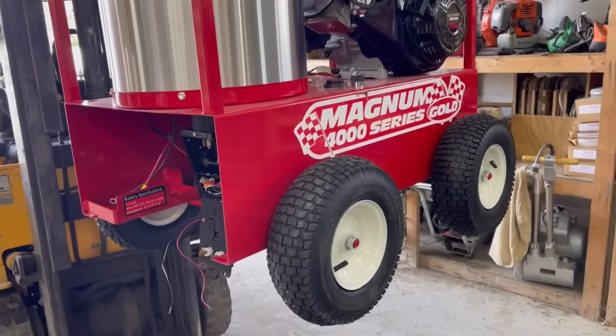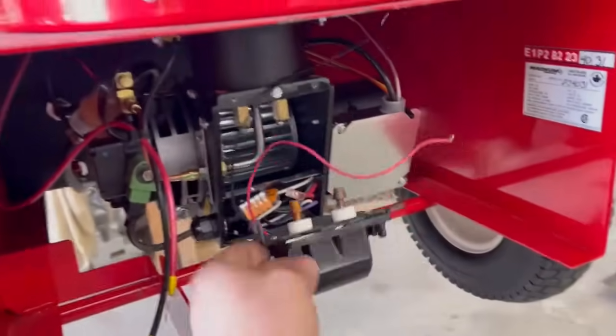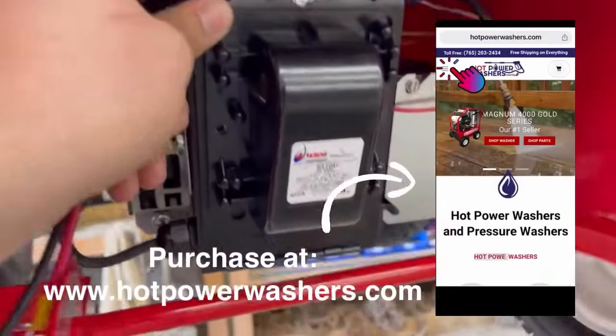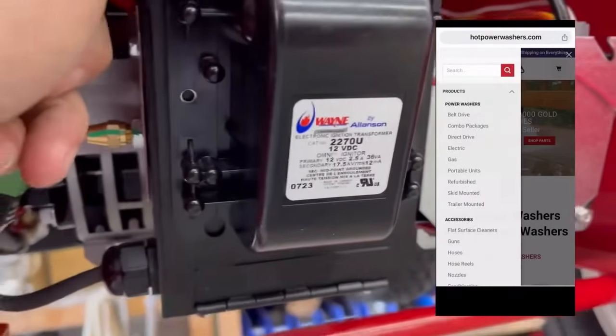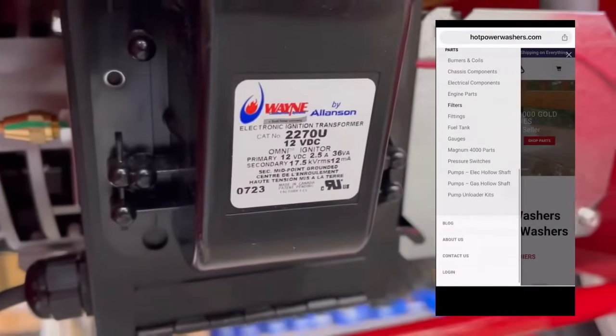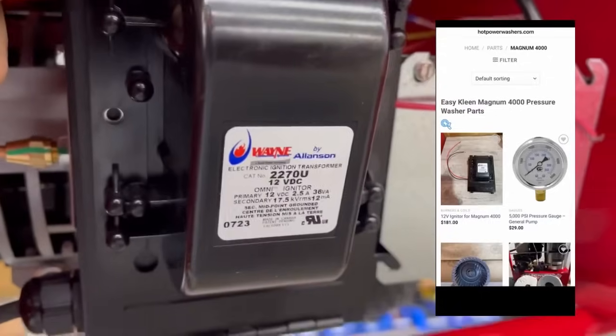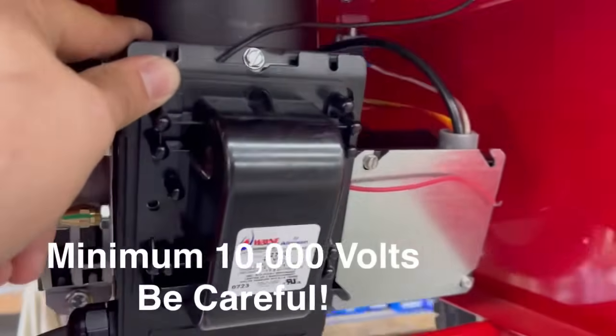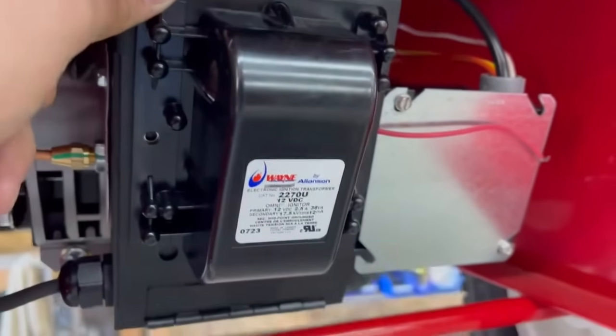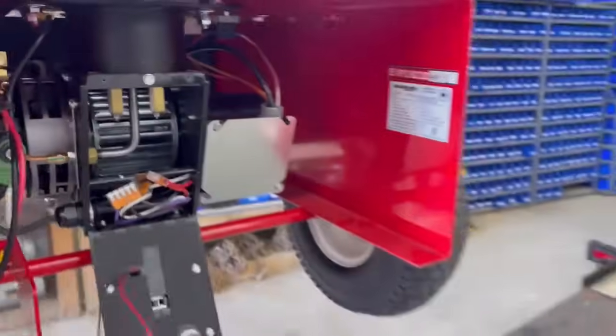This is a Magnum 4000 series gold unit and we're going to be showing you how to test this igniter transformer. It has a Wayne and according to Allanson it has an output of 17,500 volts — that's 17.5 kilovolts — so be extra cautious.